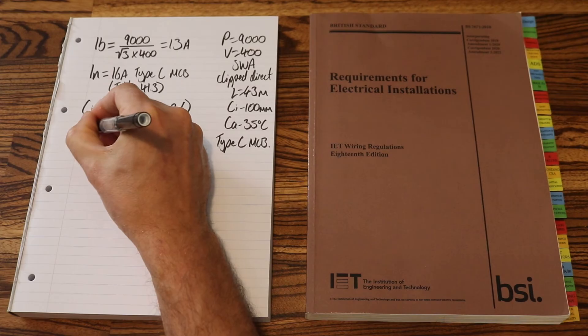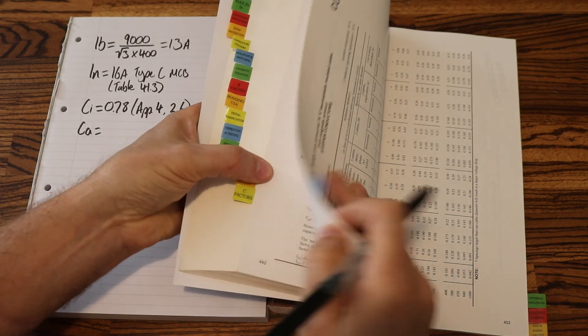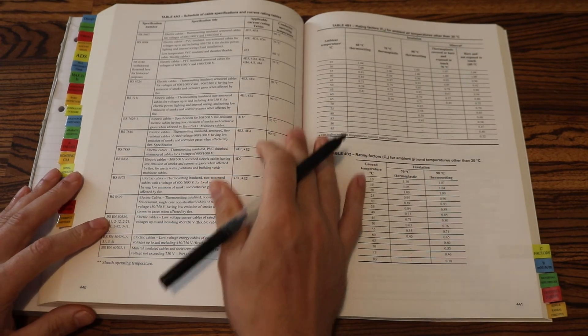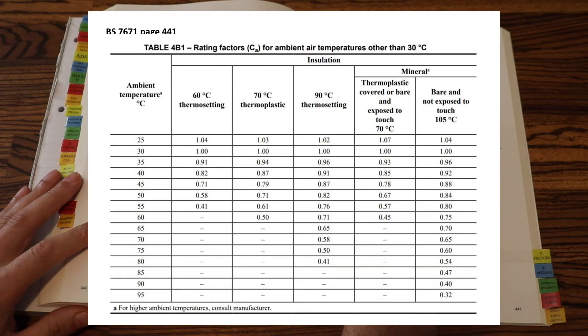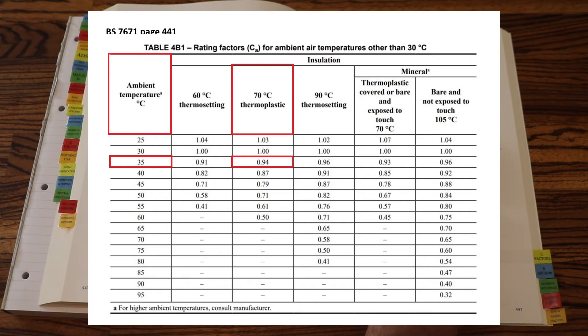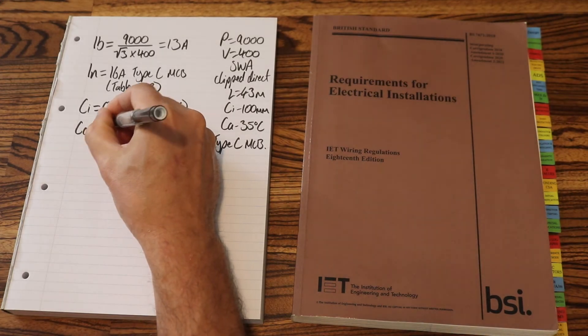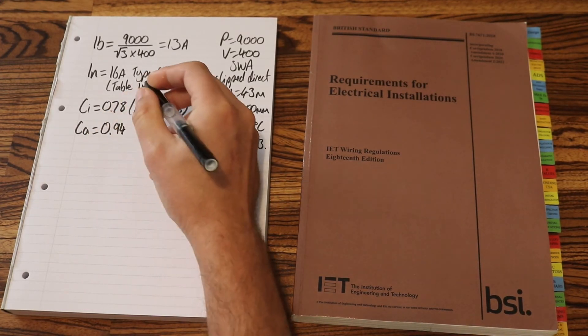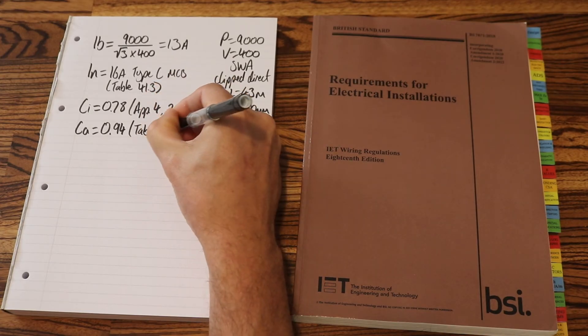Our next C factor was CA. Again, we're in Appendix 4. Now I'm looking at page 441, the top table, Table 4B1. Rating factor CA for ambient air temperature. Our ambient air temperature for this question was 35 degrees. So go down column 1, 35 degrees, and over to column 3, which was 70 degree thermoplastic cable. And we find our derating factor 0.94.